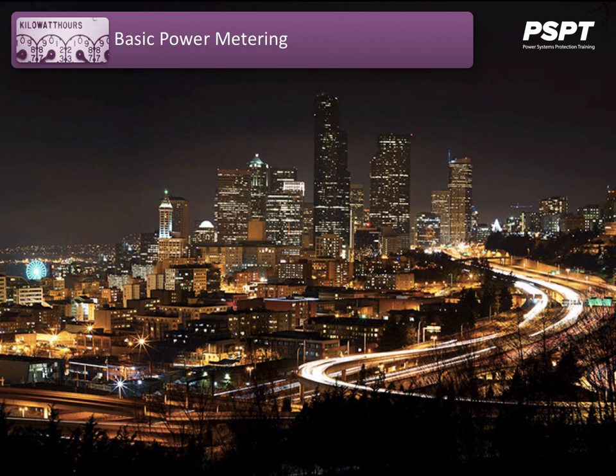Before proceeding into the next set of metering type installations, especially for three-phase metering, we have to understand that utilities have installed or will be installing hundreds of thousands of these meters in their utility system, so that as a cost-saving measure, they try to keep the numbers of watt meters down, and certainly the cost of the watt meters down. And if you reduce the number of elements in a watt meter, certainly the cost will go down, because the cost will go up as you introduce more elements into the meter. And if you have fewer elements, then you have fewer CTs and PTs that have to be connected and the associated wiring. So all in all, there is a general trend, or has been a general trend, to reduce the amount of elements involved in a metering system.